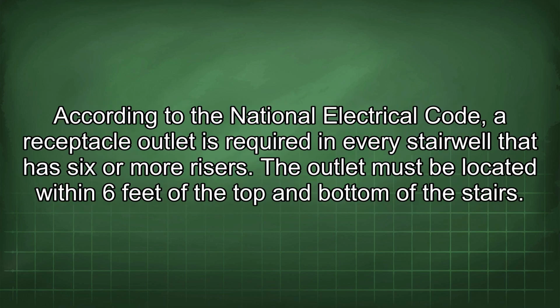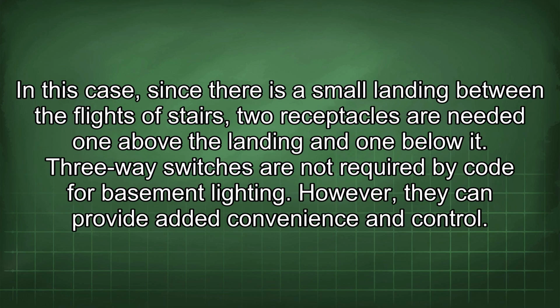According to the National Electrical Code, a receptacle outlet is required in every stairwell that has 6 or more risers. The outlet must be located within 6 feet of the top and bottom of the stairs. In this case, since there is a small landing between the flights of stairs, 2 receptacles are needed, one above the landing and one below it.